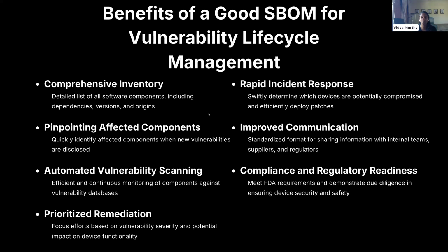The biggest headache is if you start with a messy software bill of materials, you're just going to be struggling at every other step of vulnerability management. So my biggest recommendation for monitoring is you could go down the path of going to the NVD. You could use the MedISAO portal and start looking for components. That's probably a good place to start practically.